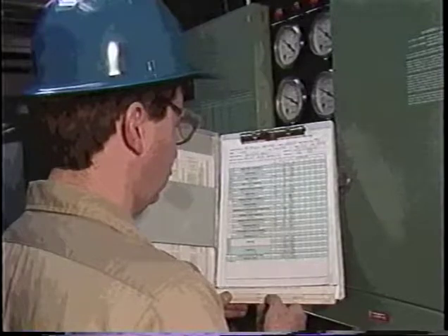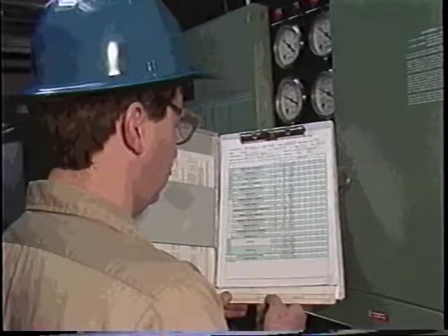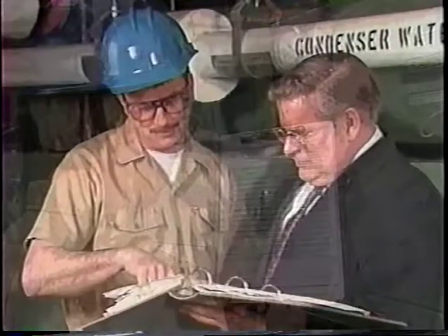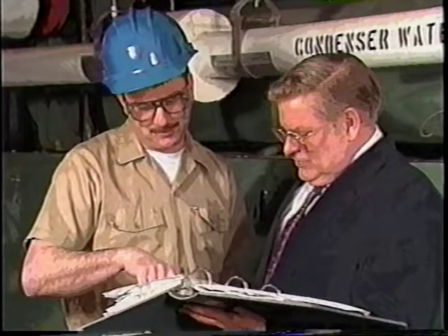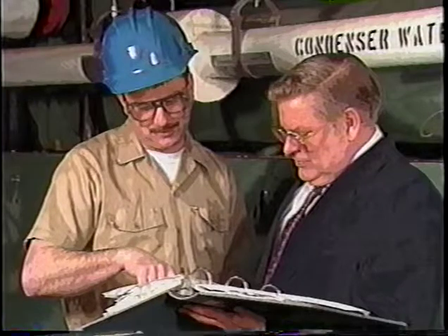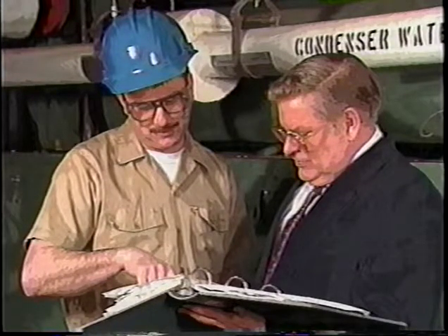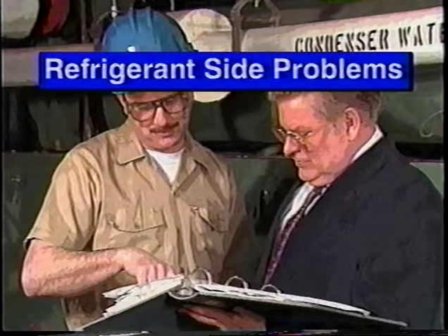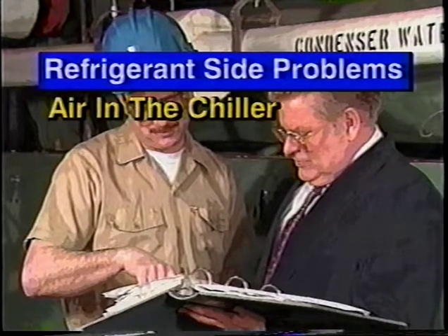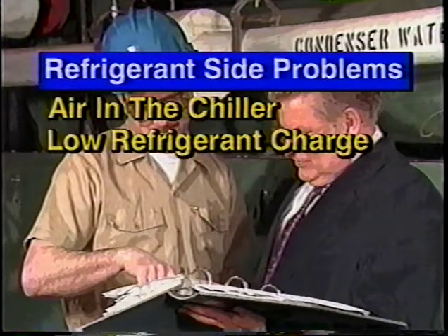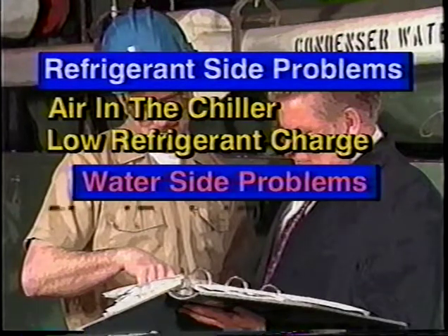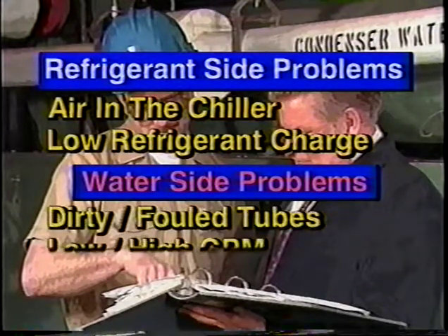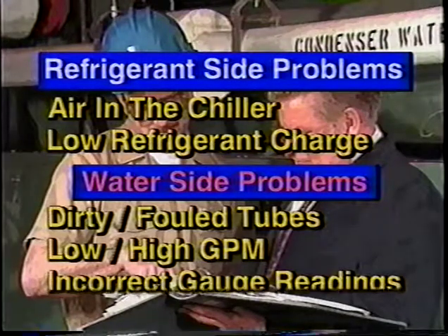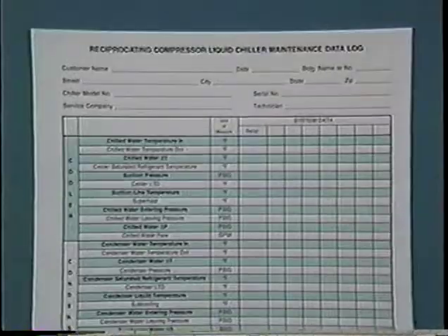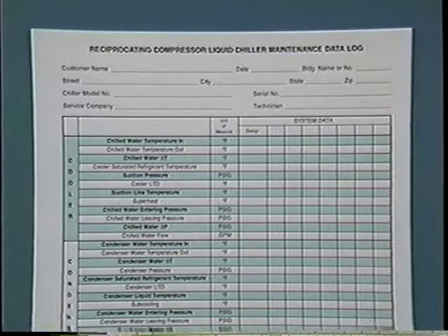After taking the readings, compare the current operating temperatures and pressures with the design conditions and previous operating conditions to spot any trends which might be leading to trouble. Using the log sheets will help identify refrigerant side problems, including air in the chiller, low refrigerant charge, or water side problems, including dirty or fouled tubes, low or high GPM, and incorrect gauge readings. Now let's take a closer look at the log sheet and discuss each of the entries, starting first with the cooler section.